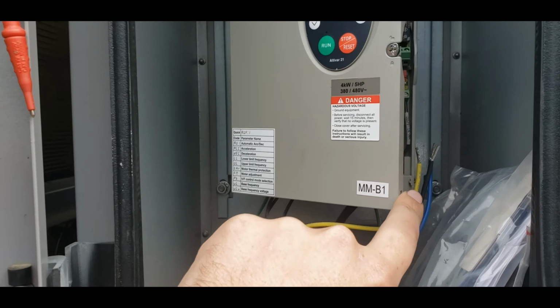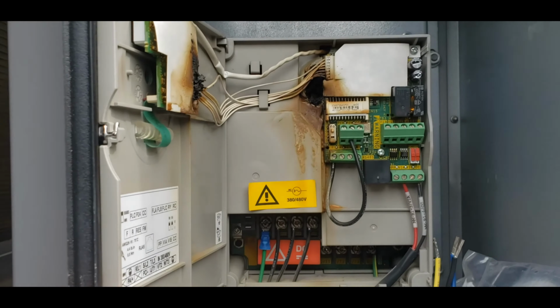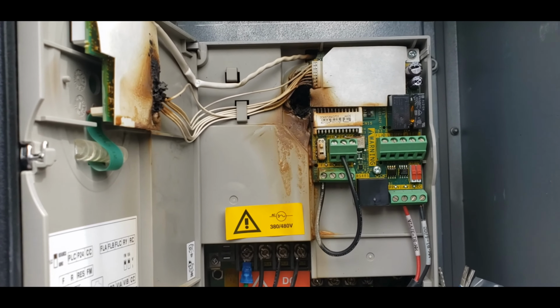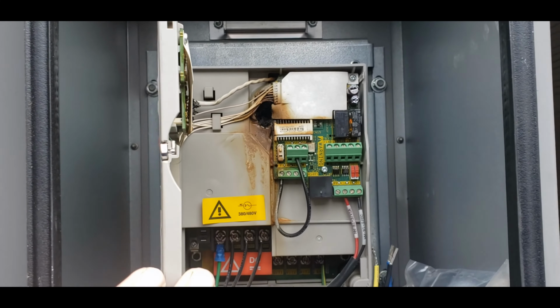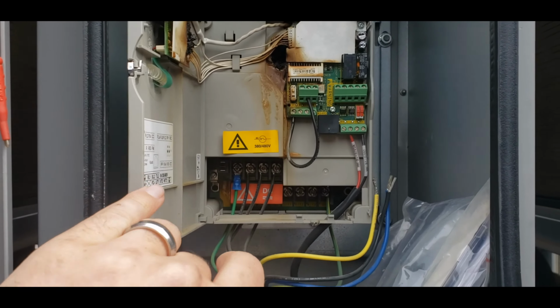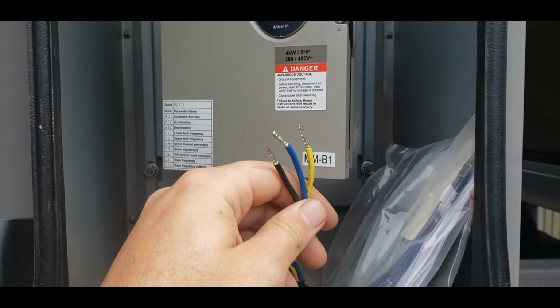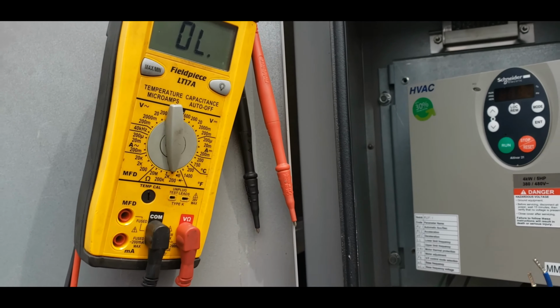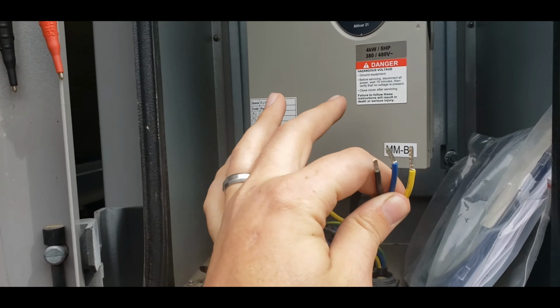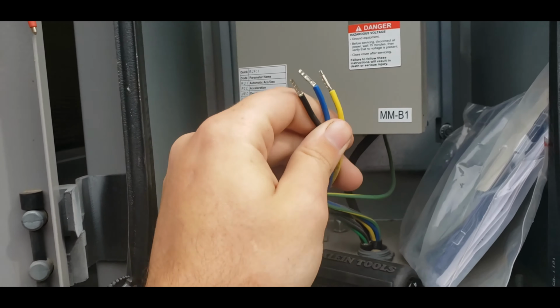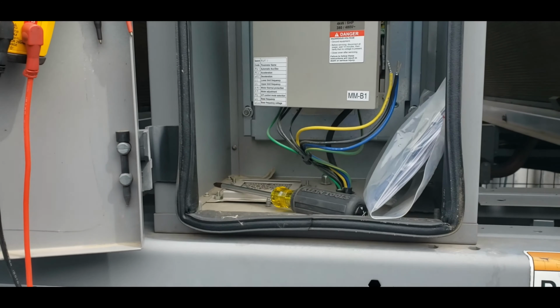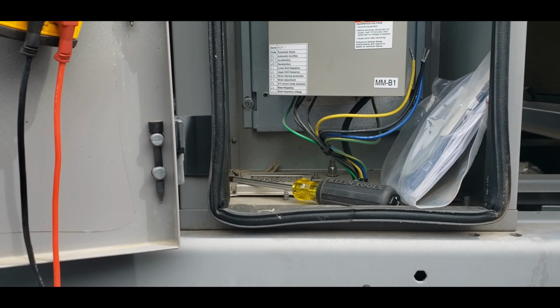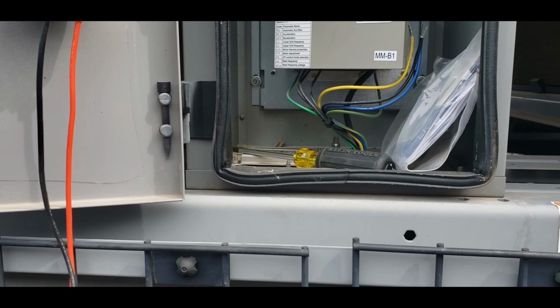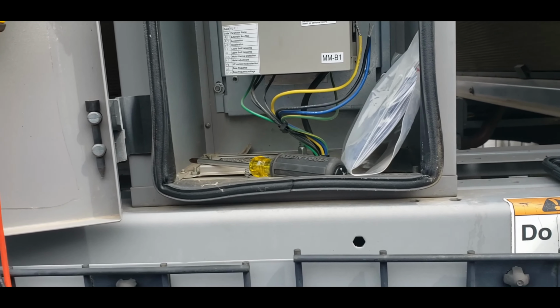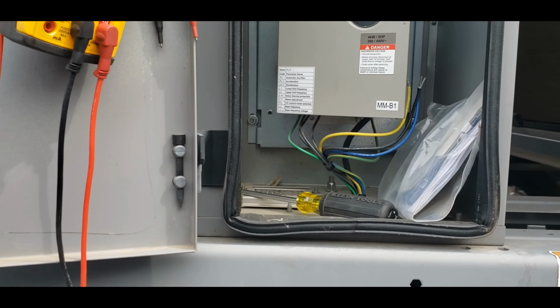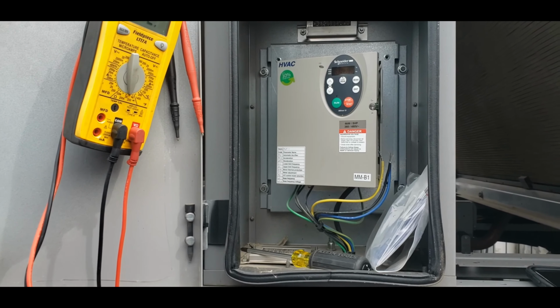So while going through the PM over here on these Carriers, this is a B1 condenser fan motor. It's the VFD that controls it. It obviously shorted out, blew up. Now I've tested the motor with just my regular meter, and it tested good. But I'm also going to go get my megger. I'm going to meg that motor just to be sure that there's not any question as to whether it's going to hold up or not. But as of right now, we'll get all that sent off to the customer, and it'll be up to them to decide whether or not they want to get it fixed and when.